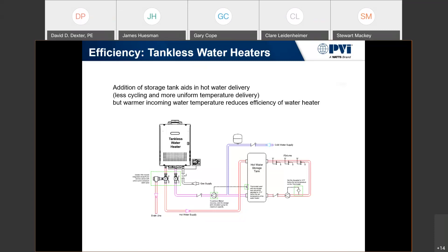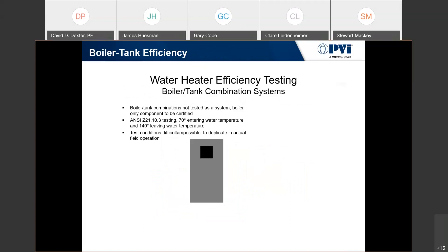You still have your loop with your return, but you're pulling out of the hot water storage tank. There's another pump bringing water back into the tankless water heater, feeding it through the hot water supply into the storage tank. At the same time, we're still mixing that water going into the tankless water heater. This is also true with boilers — it's the same standard and the same ANSI Z21.10.3 test.